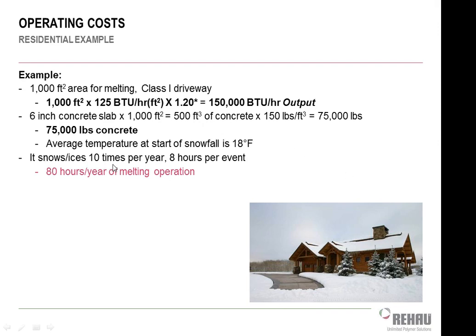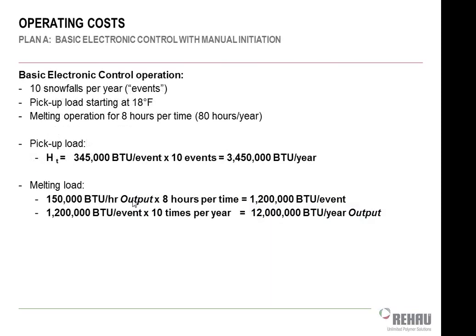Say here, if we have an average of 10 snowfalls a year and it snows for 8 hours per snowfall, that's 80 hours of snow melting operation that I'd be paying to heat this driveway. If I decided to do that with the basic electronic control, this gives you just an idea of my pickup load and my melting load. My pickup load is basically to get this whole giant slab of concrete up to the temperature that I need it to be at. So that corresponds to a certain number of BTUs per year. In this case, 3.5 million. That's per year, right? So you're not running a 3.5 million BTU boiler. That's 3.5 million BTUs per year, not per hour.